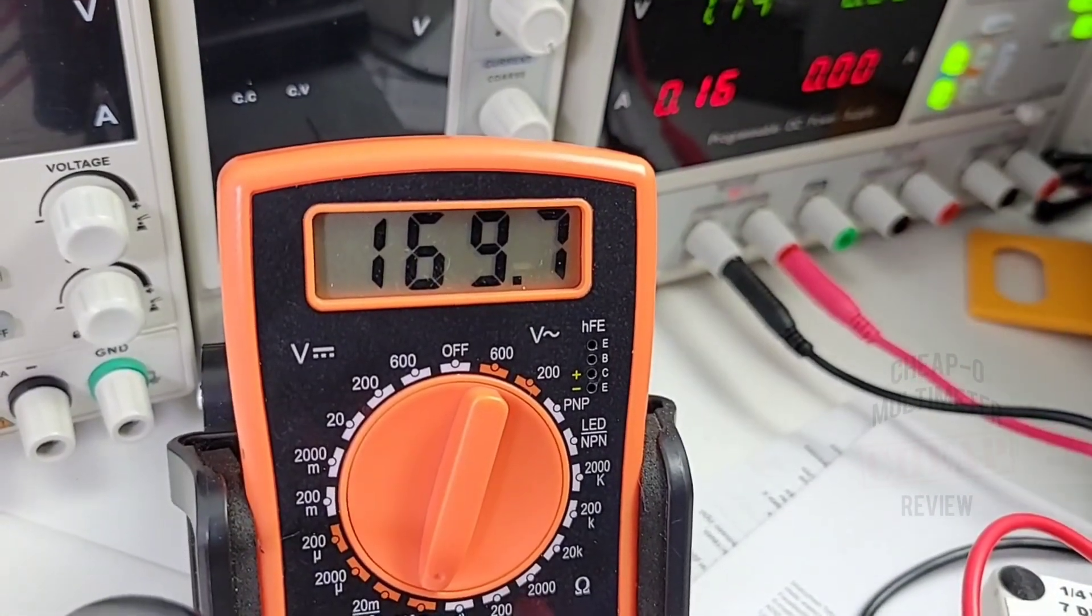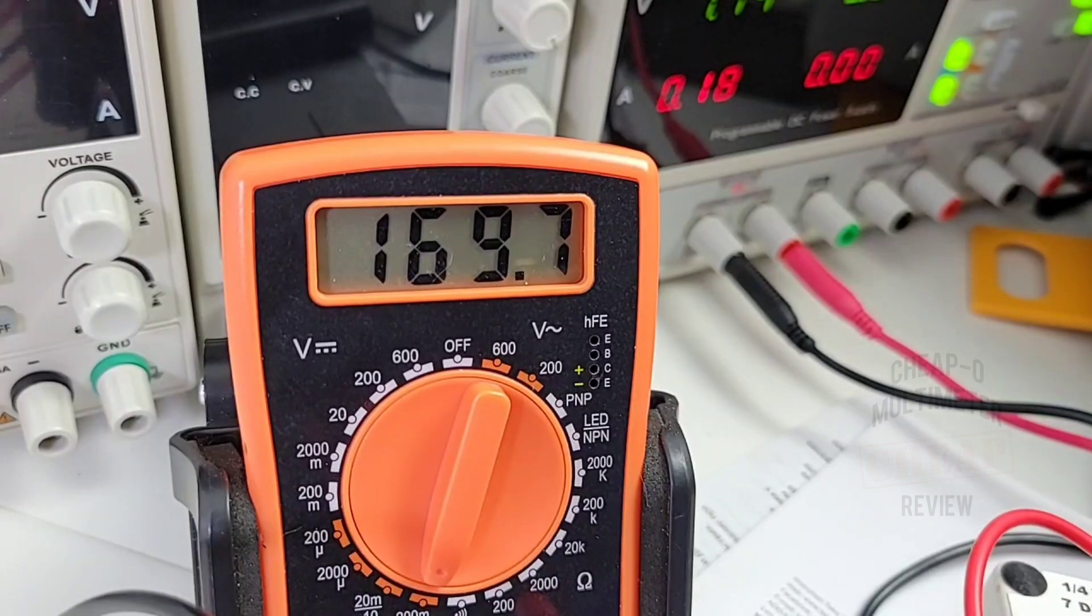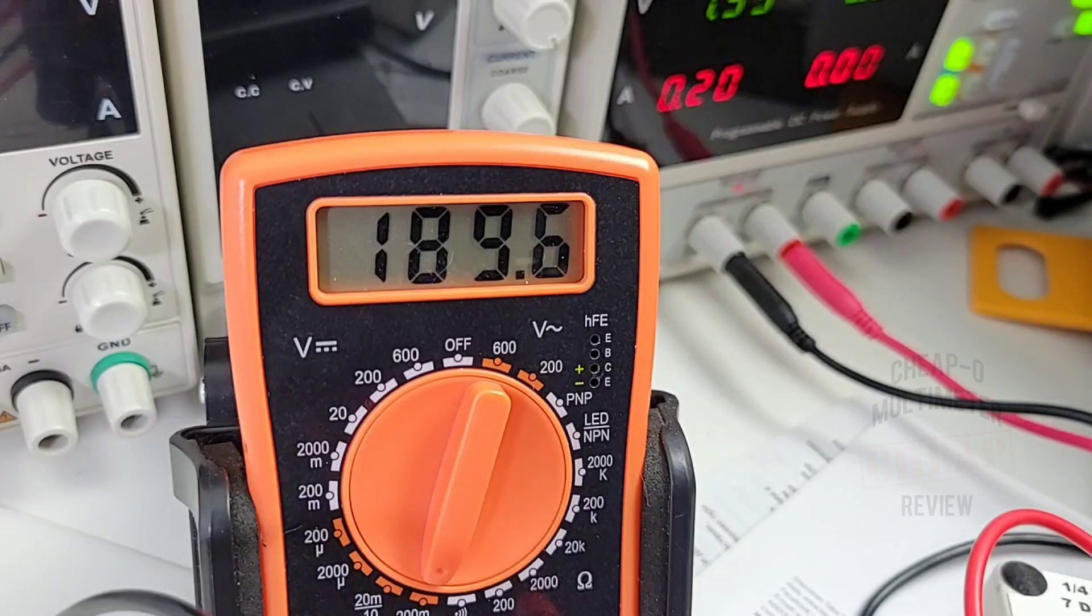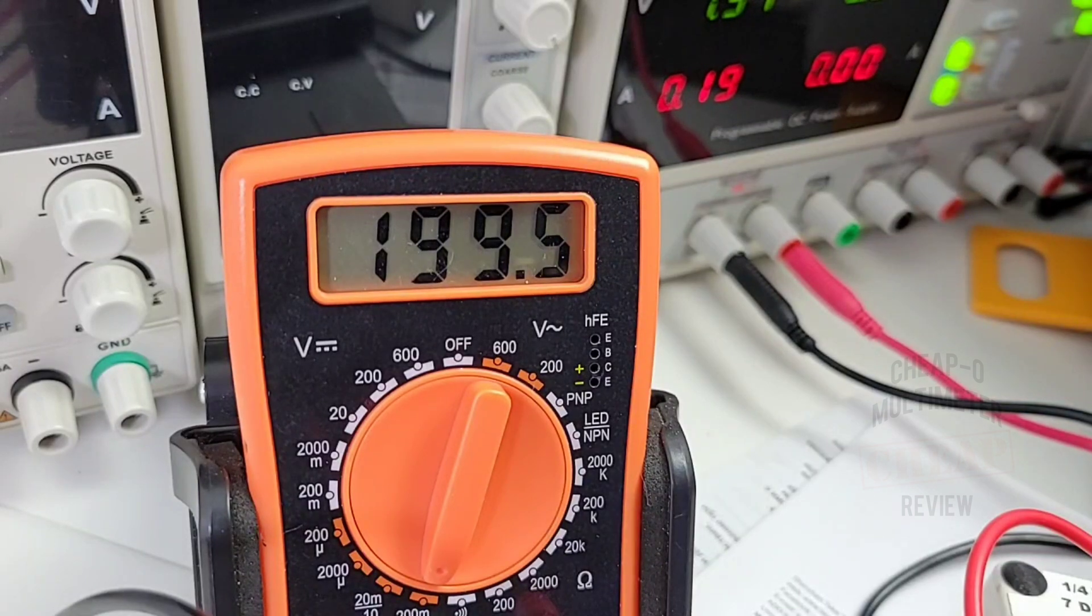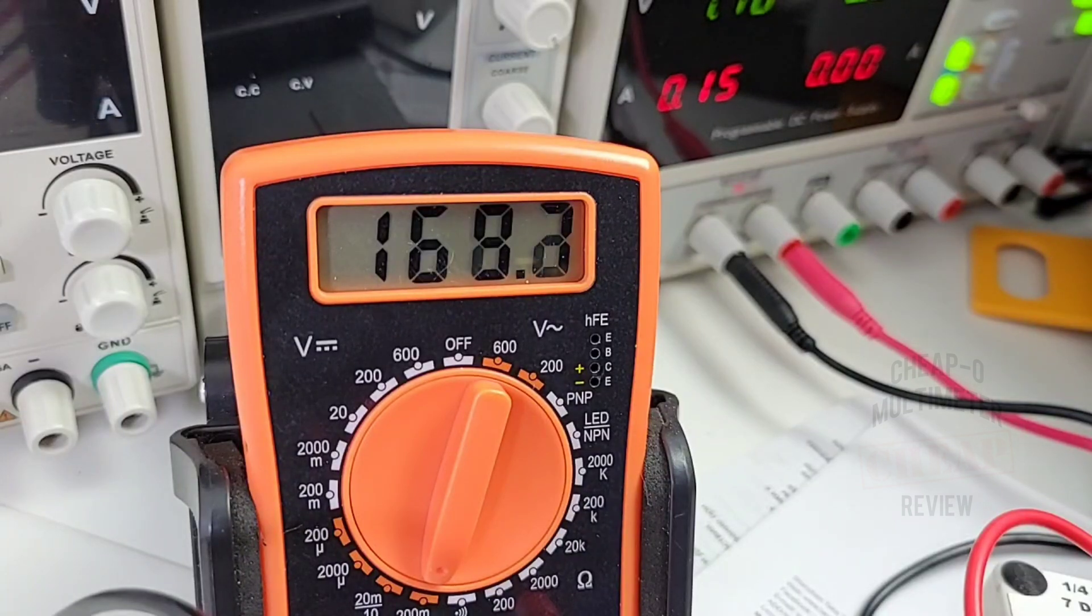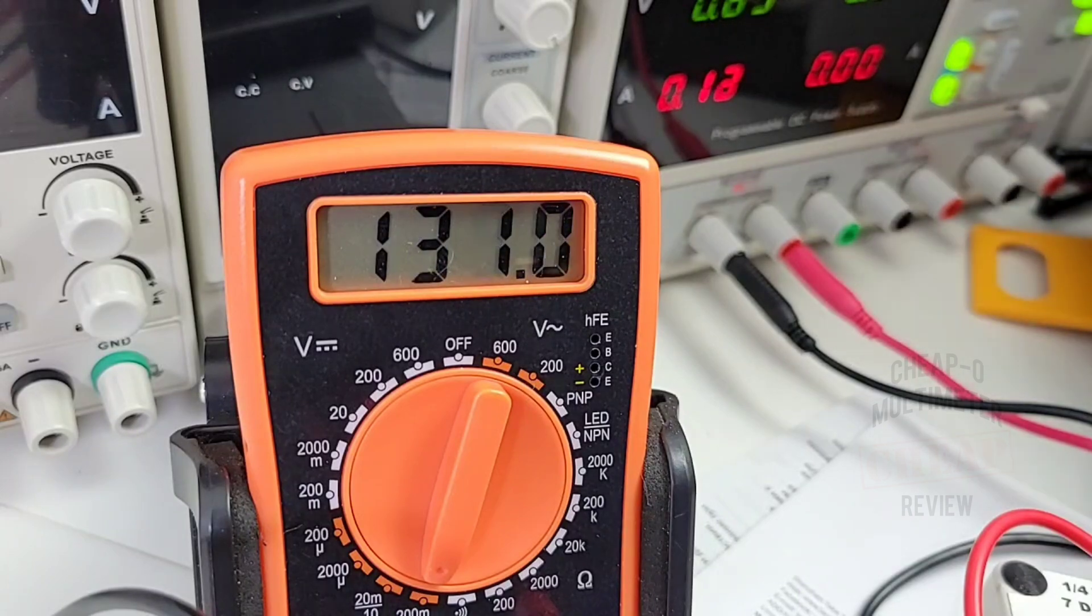We will bring it up incrementally here: 190, and 199. Remember, 200 milliamps, that's the threshold, and now we're over limit. So that threshold is holding true. All in all looks pretty good, no issues, love it.